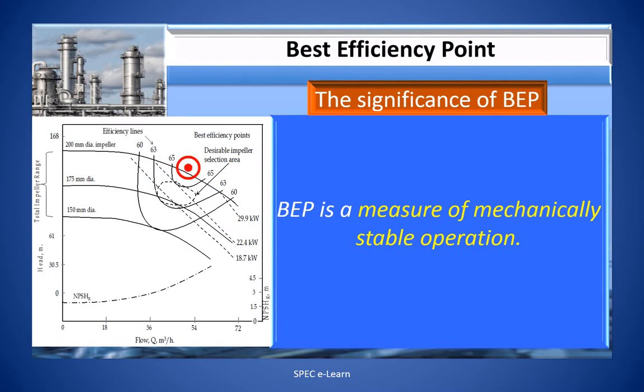BEP is also a measure of mechanically stable operation. The impeller is subject to non-symmetrical forces when operating to the right or left of the BEP, which manifest in mechanically unstable conditions such as vibration, excessive hydraulic thrust, temperature rise, and erosion. An increase in process fluid temperature in the pump casing causes seizure of close-tolerance spots and cavitation. Sustained excess velocity and turbulence result in vortices capable of damaging the pump casing, backplate, and impeller, while also inducing premature bearing and mechanical seal failures due to shaft deflection.